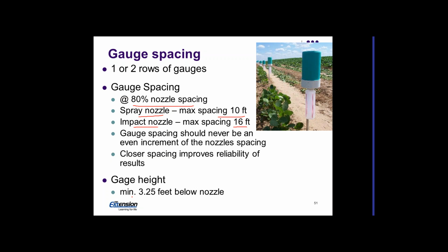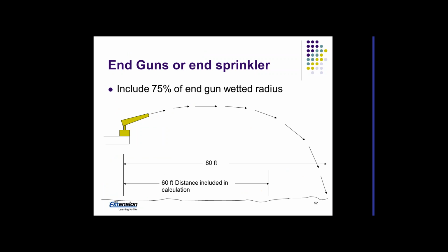There also, we need a minimum height of 3.5 feet between the top of the gauge and the sprinkler. So that's basically so that when the water's coming out, it's coming down into the gauge. So if this was my cup here, we don't want it to come sideways into the cup. We want it to be coming down into the cup. So that's the reason for that.